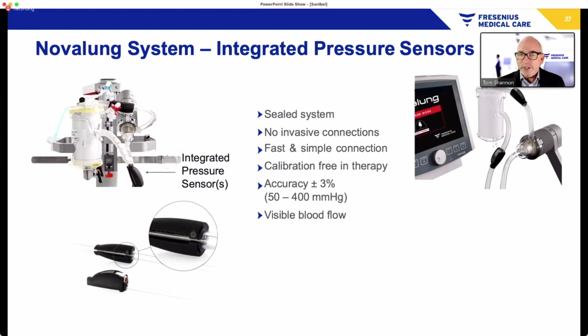And again, the integrated pressure sensors, which I mentioned, and I'll leave you with just a look at the screen. For those of you who aren't familiar, it's a 10-inch touch screen where you can monitor 3 pressures simultaneously, as well as the delta pressure, so 4 pressures displayed on the screen. We also have the ability to trend data over minutes, hours, days, weeks. We have some unique features with respect to setting alarms, where you can automatically set alarms at plus or minus 20% for every parameter with a one-touch feature. So it's quite the unique system.